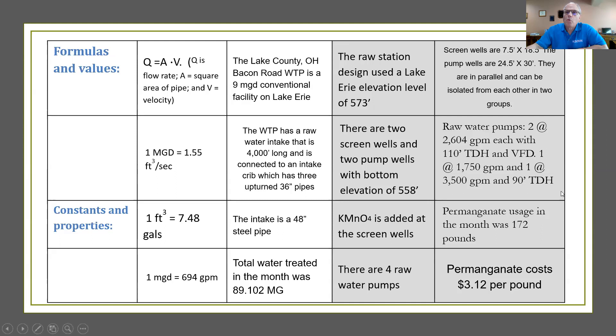Now there are four raw water pumps. Two of them are 2,604 gallons per minute each with 110 feet total dynamic head with a variable frequency drive on them. We also have two fixed speed pumps. One of them is a small pump at 1,750 gallons per minute. The other is a larger pump at 3,500 gallons per minute. Each of them has a total dynamic head rating of 90 feet. Goes on to say that permanganate usage in the month was 172 pounds and it gives you a cost of $3.12 per pound for permanganate.